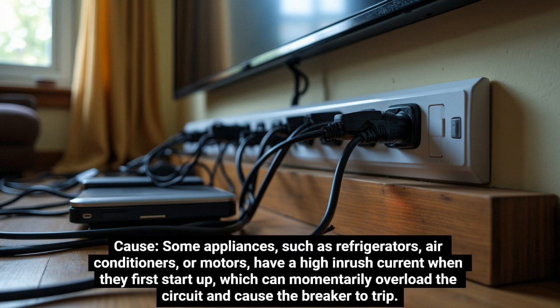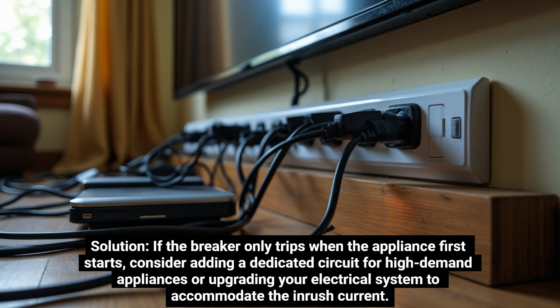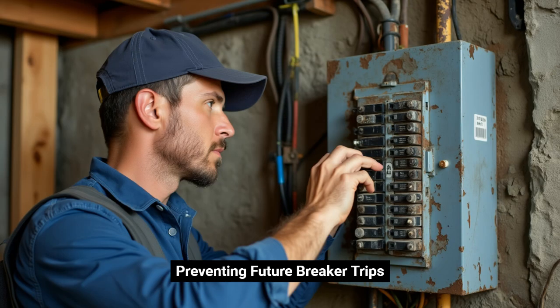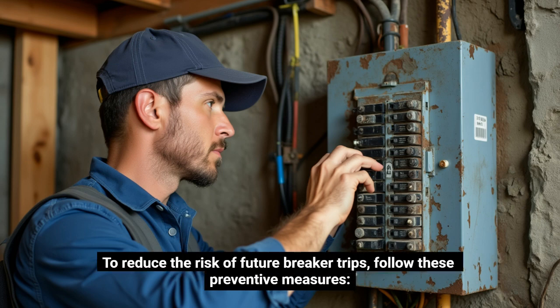Cause: some appliances, such as refrigerators, air conditioners, or motors, have a high inrush current when they first start up, which can momentarily overload the circuit and cause the breaker to trip. Solution: if the breaker only trips when the appliance first starts, consider adding a dedicated circuit for high-demand appliances or upgrading your electrical system to accommodate the inrush current. Preventing future breaker trips. To reduce the risk of future breaker trips, follow these preventive measures.